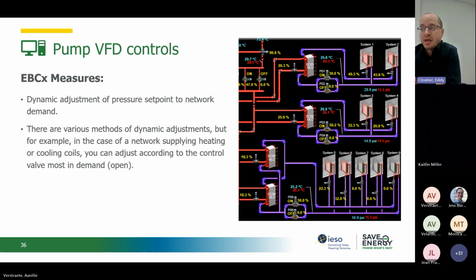For the implemented measure, we modified the programming of the pumps to analyze the demand of the different heating coils in the system. So the pressure has been dynamically adjusted so that when heating demand is low, the static pressure set point is automatically reduced. This measure makes it possible to significantly reduce the speed of the pumps and, of course, their energy consumption. Next slide.